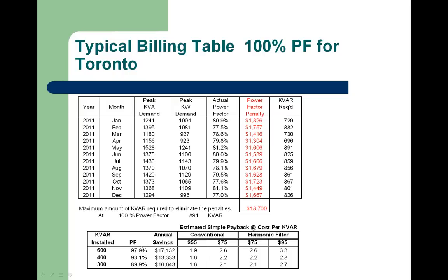So in the bottom table down here, we can see that 600 kVAR would give them an average of 97% power factor with about $17,000 in annual savings. And if we went down as low as 300 kVAR installed, they'd have an average power factor of a little less than 90%, and still have $10,000 in annual savings. Sorry, $10,000 annual savings, and these are the associated paybacks. So again, if somebody had a maximum 3-year payback, and it was a high-cost filter that required disconnect switches or more cable because it was further away from the main switchboard, they may want to go with less than 400, down to 400 kVAR or so.